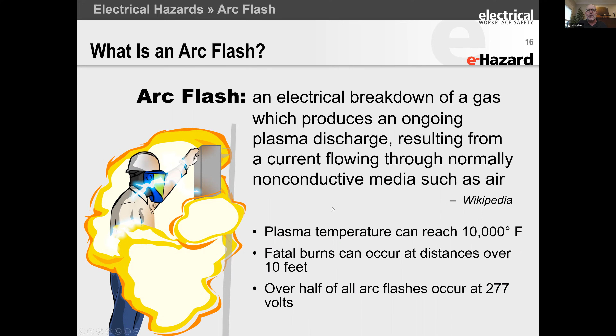An arc is around 10,000 degrees Fahrenheit, which is around 5,000 degrees C, the temperature of the plasma. It can be a little bit more, a little bit less, but that's typically plasma and air. But the temperature of plasma is not what's really important. What's really important is the plasma density. The plasma density at the roots of the arc is very high, and the temperature is high. And then as you come away from that arc root, it goes down in temperature quite dramatically. The infrared piece is going down in its total energy, and the hot gas ball is going down in temperature. But a third of a meter away, you can still be at 2,000 or 3,000 degrees, which is more than enough to ignite any clothing and melt any clothing. The plasma density just gets lower and lower until it becomes pre-plasma.